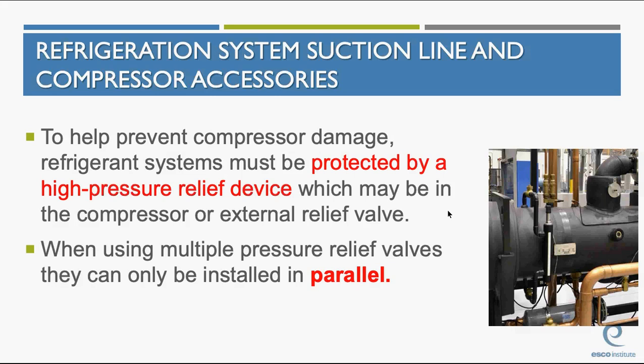To prevent compressor damage, the refrigeration system must be protected by a high-pressure relief device, which may be in the compressor or it's an external relief valve. When using multiple pressure relief valves, they can only be installed in parallel. Okay, look real close at this picture over here. I'm going to circle 2 pressure relief valves. Notice they're installed next to each other. They are installed in parallel.